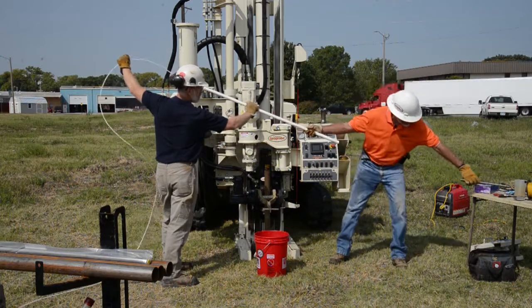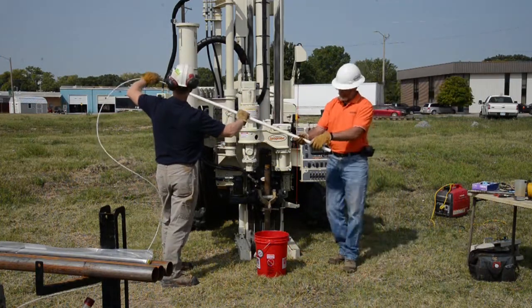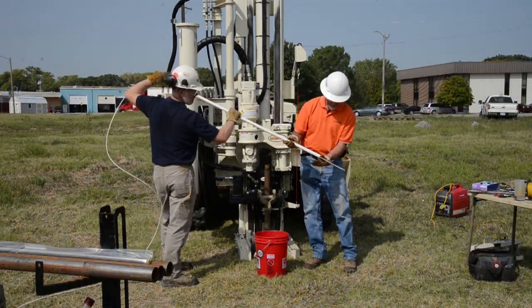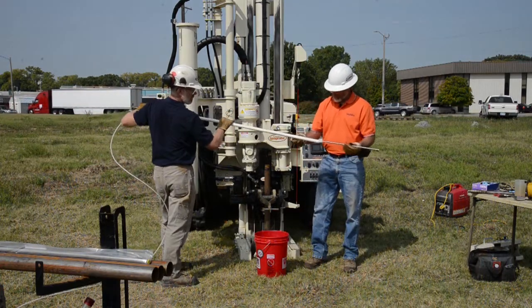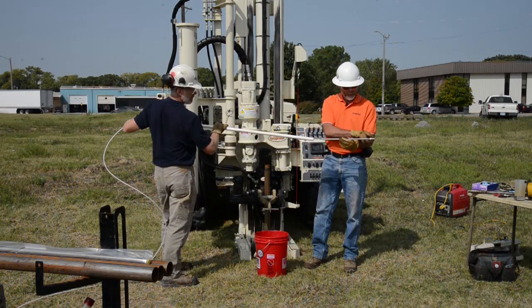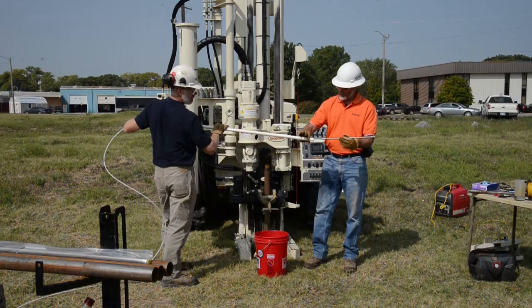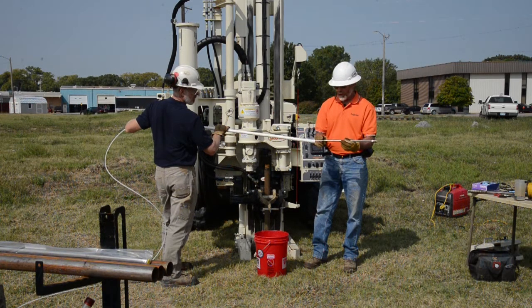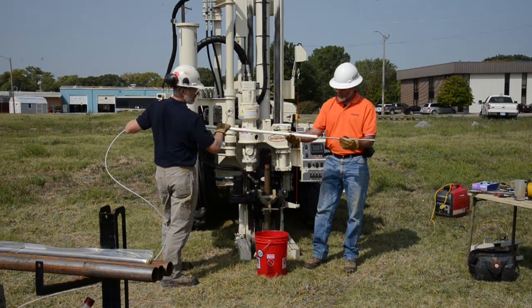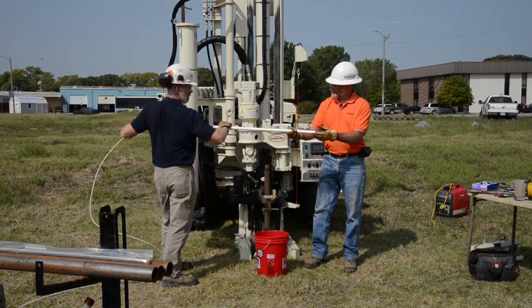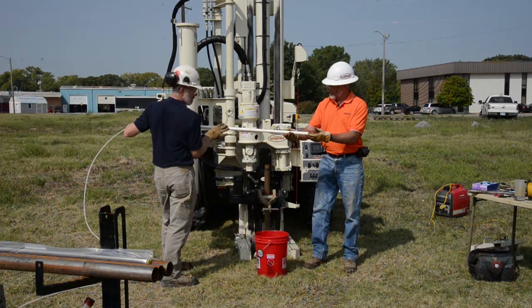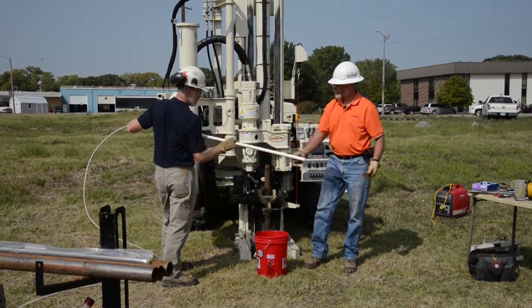Okay, I'll lay this aside to be cleaned up. Dan will push out the pump for us. There we go. So again, here you can see our pump with the seal on the end that seals inside the PVC, and our pump body where our tubing is attached with a crimp here on our barb fitting. So we recover our system that provides a sealed, isolated sample from the screen interval.